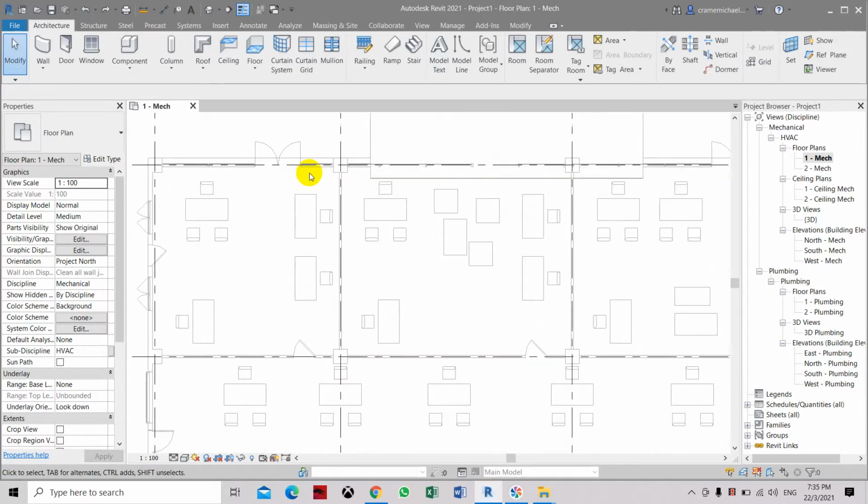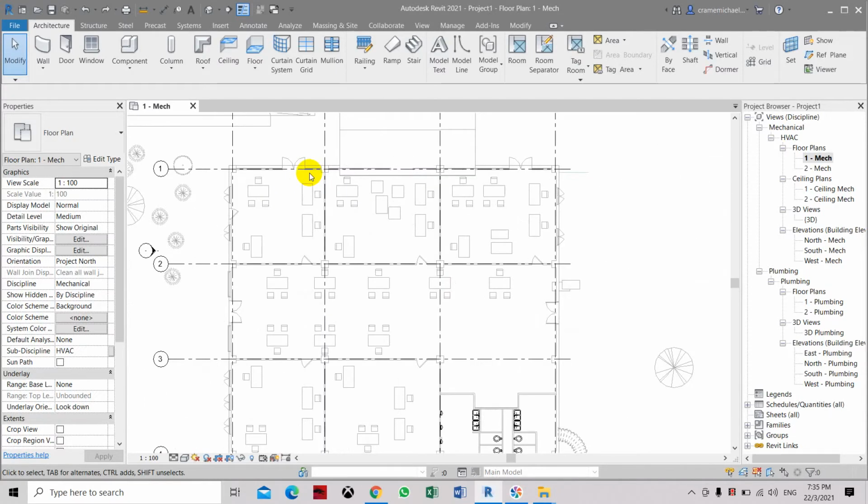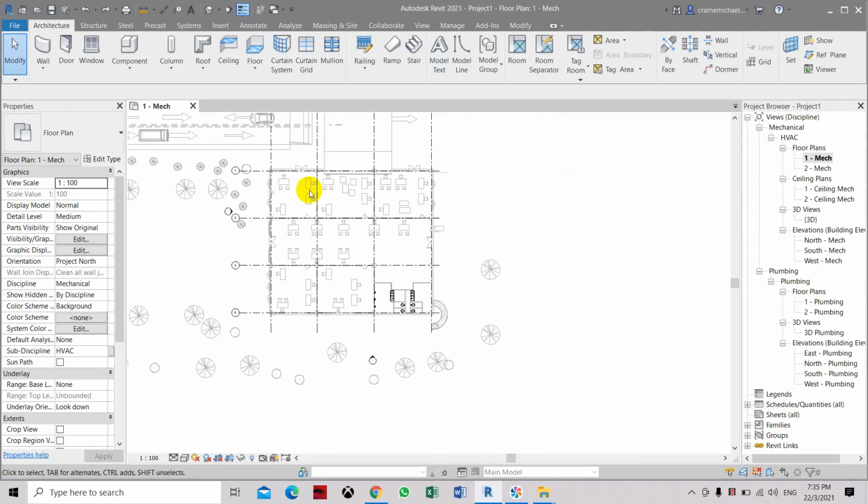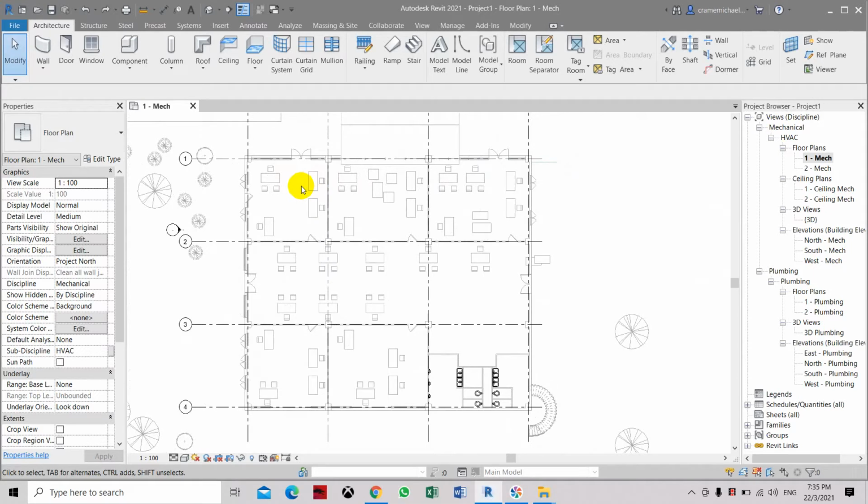which is the curtain wall or the facade, should have the correct glass properties such as the U value and shading coefficient, the thickness of the material of the glass, and also the color. So basically, all these properties will be used in the cooling load calculation. So now what we need to know first is the floor area of each individual room.